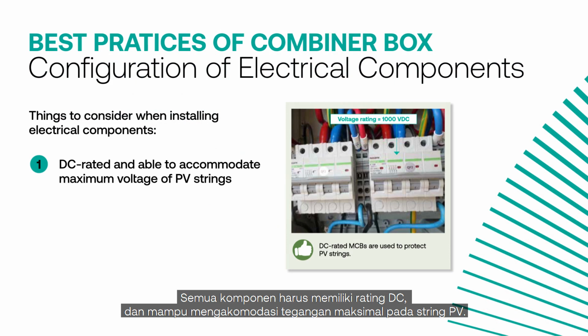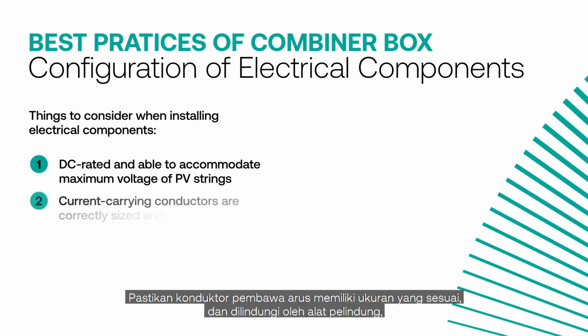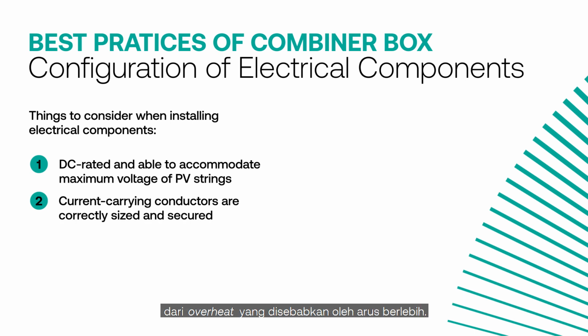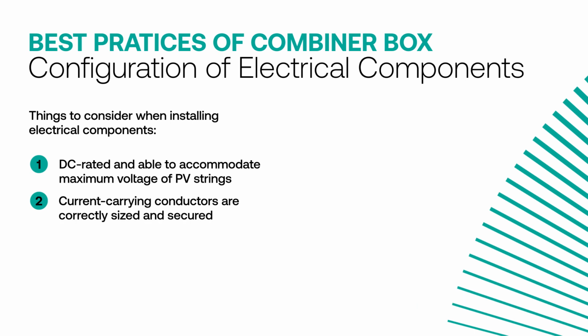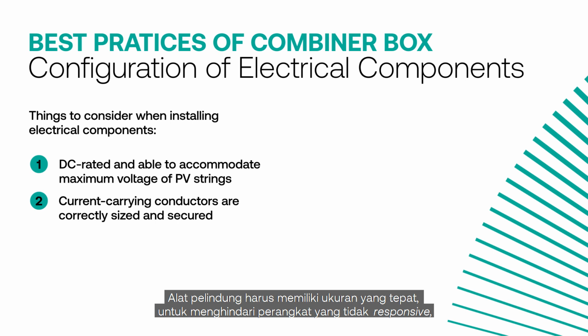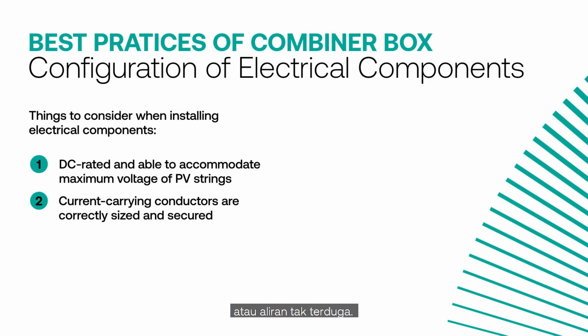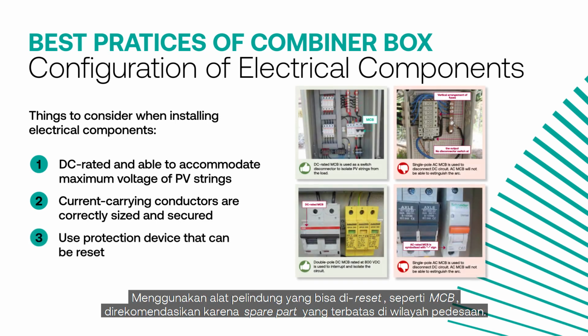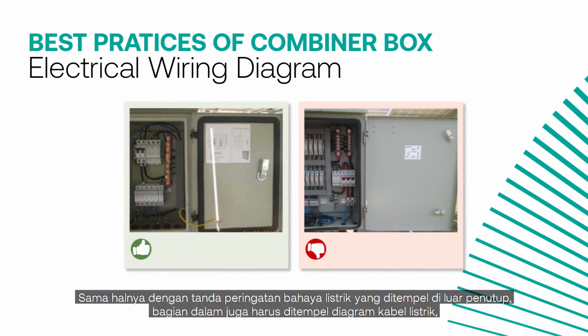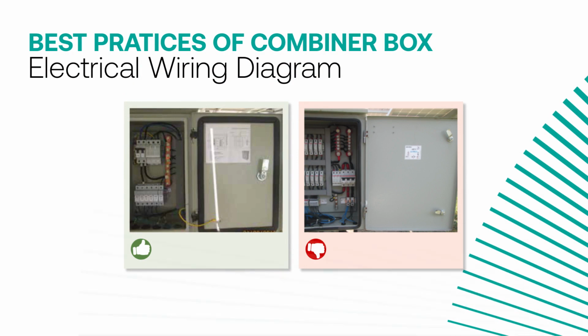All components should be DC rated and able to accommodate voltage up to the maximum voltage of the PV strings. Ensure that the current carrying conductors are correctly sized and secured by protection devices from being overheated caused by excessive current. Protection devices should also be properly sized to avoid unresponsive devices or unexpected trip. Using a protection device that can be reset, such as an MCB, is recommended due to the limited spare parts in rural areas. Similar to the electrical hazard warning that is attached outside the enclosure, the inside part of the enclosure should also have an electrical wiring diagram attached to easily identify components.